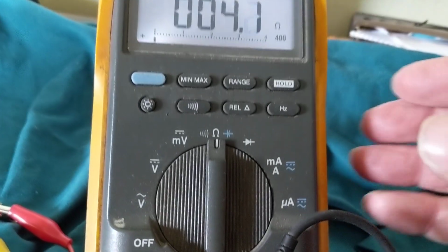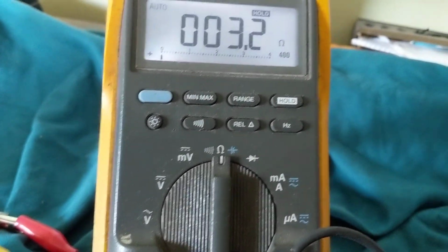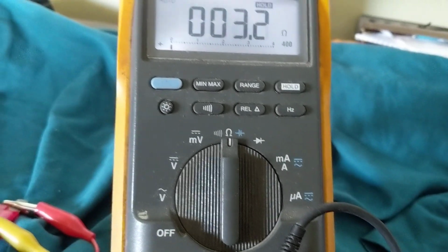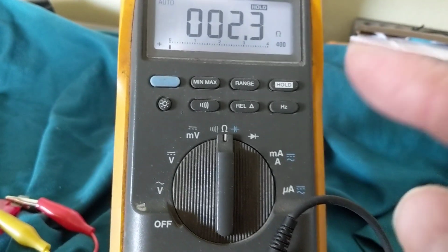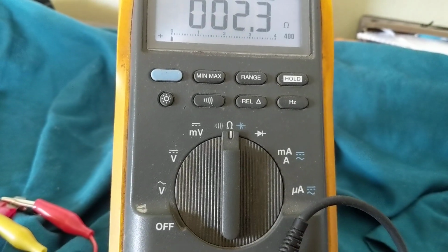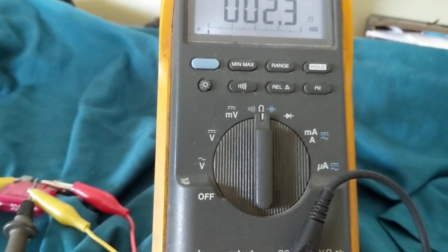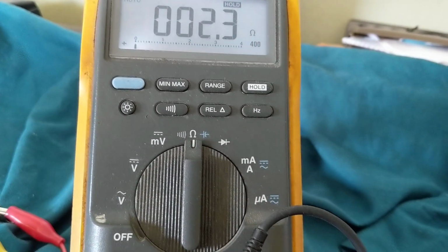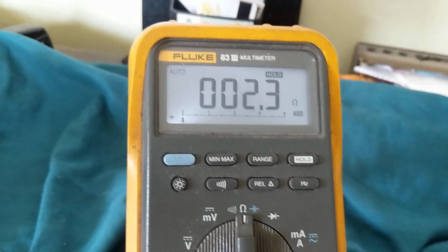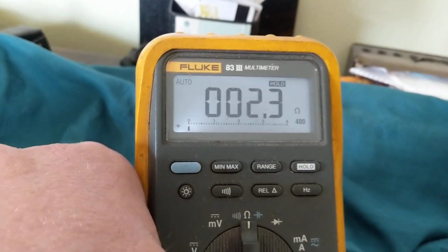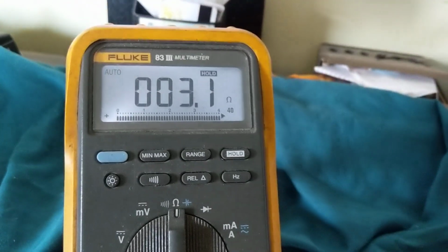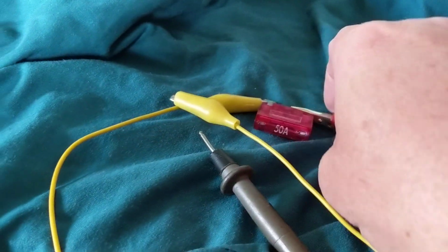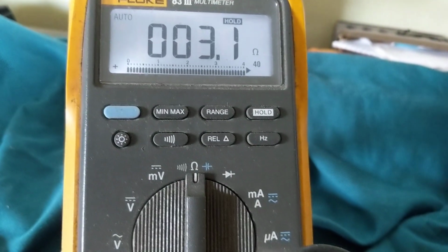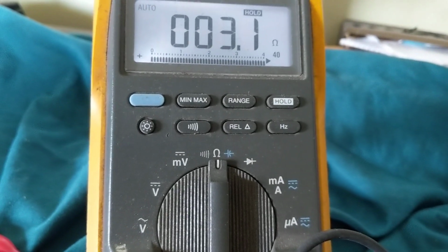Okay? Now, the hold function, as we spoke about before. This is on hold. What does it mean? Hold means you're putting it in memory. So the last measurement that it detects will be put in memory. When I take the probe away, it will hold it in memory. I don't need to keep the probe on it. As you can see, I don't have anything connected to it. There is nothing connected to the probe, yet the hold function tells me that when I measured the fuse, I measured 3 ohms, which is good.